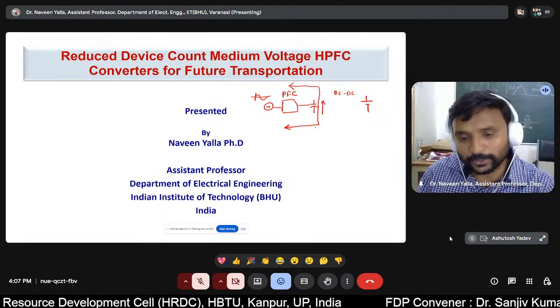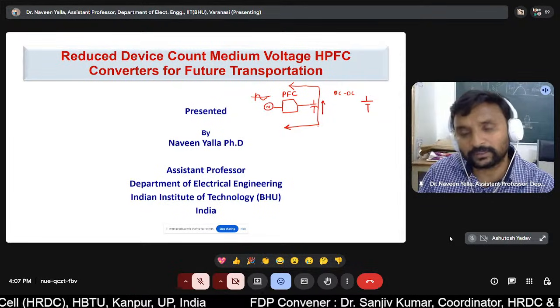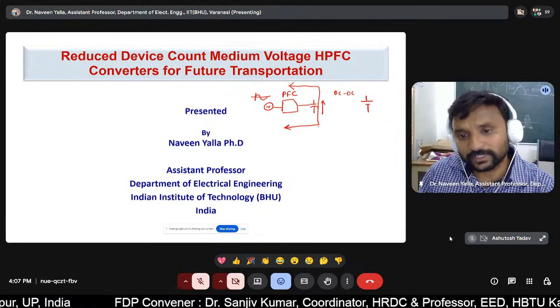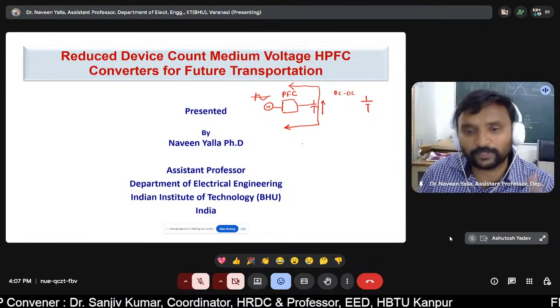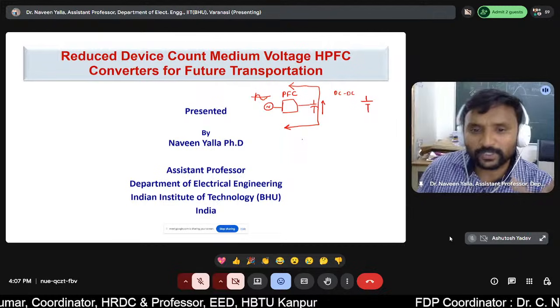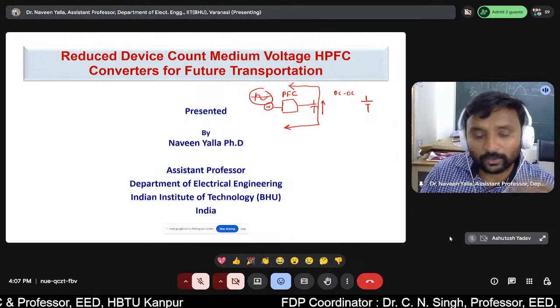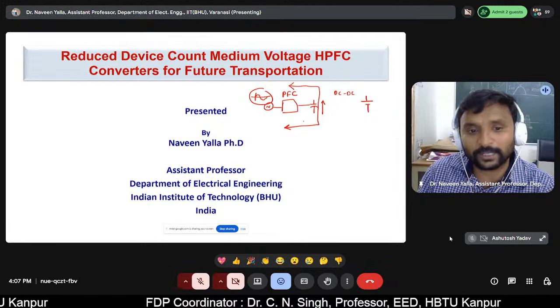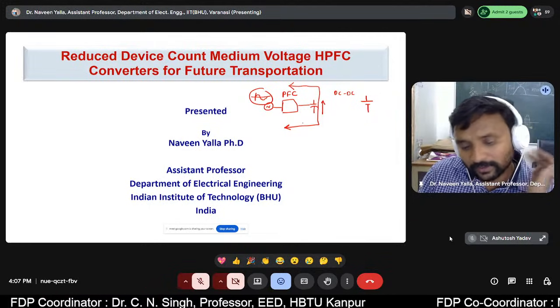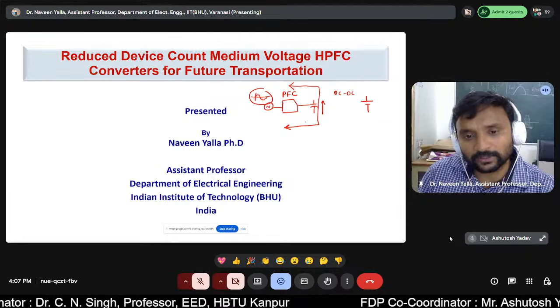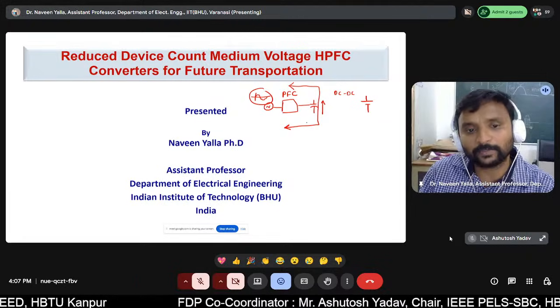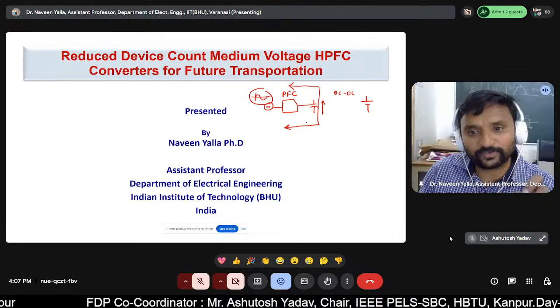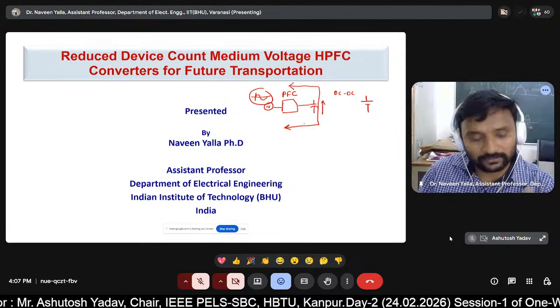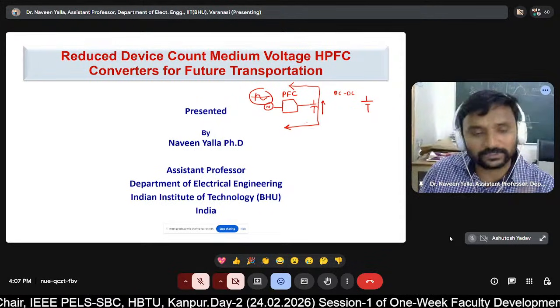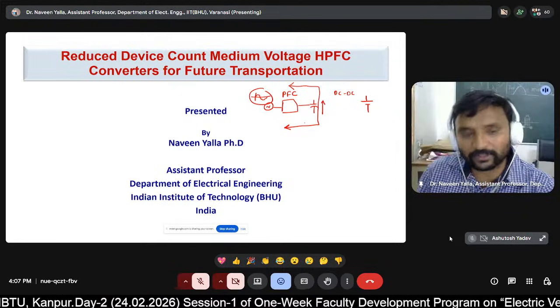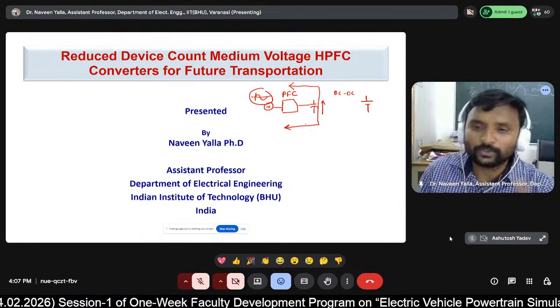This is because grid codes and standards put limitations on this. For example, IEEE 519-2022 mentions not only overall THD but also specific harmonic amplitude limits. The dominant harmonic, for instance the fifth harmonic, must have amplitude less than some specific value if the current drawn by the load exceeds a certain level, for example more than 20 amperes.